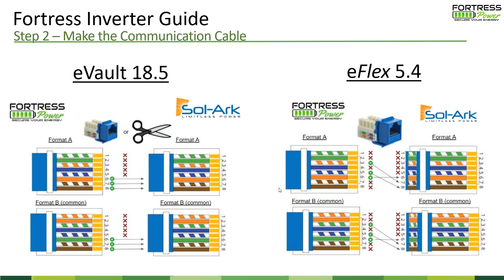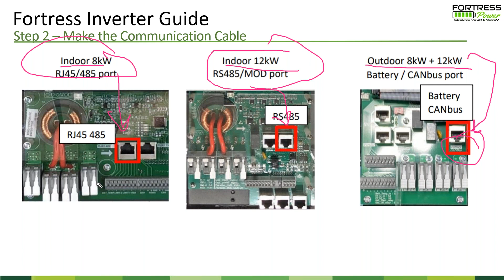The actual port that you land the communication on is going to vary by the model number of the Sol-Ark. So if you're buying your projects now, you're going to be landing on the battery CAN bus port. If you have open loop on existing projects and you are using the indoor 12 kW unit or 8 kW unit, you may land on a slightly different RS485 port. After you make that communication crossover and land on the appropriate port, then you want to give your closed loop settings a visual inspection to make sure all the data programmed over.